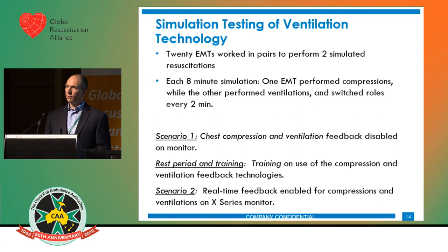So in terms of testing, we did some basic testing in the lab. 20 EMTs worked in pairs, performed 2 simulated resuscitations, so 8 minutes broken down into 2-minute cycles. 2 minutes of CPR while a provider ventilated for 2 minutes, and then they swapped. The first scenario was chest compression, ventilation feedback was disabled, just measured. Then we did some training, went back, turned all the feedback on, and then reassessed.